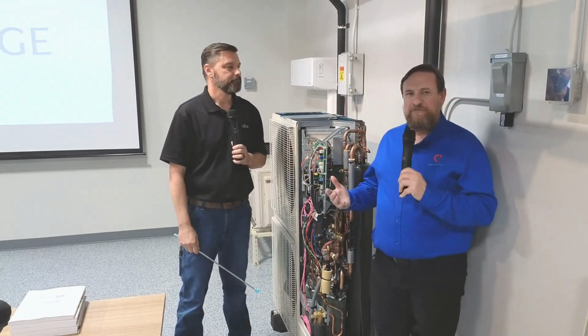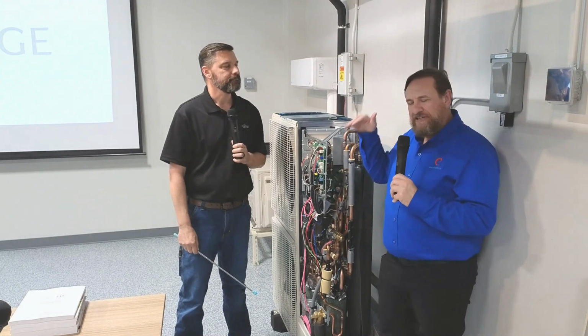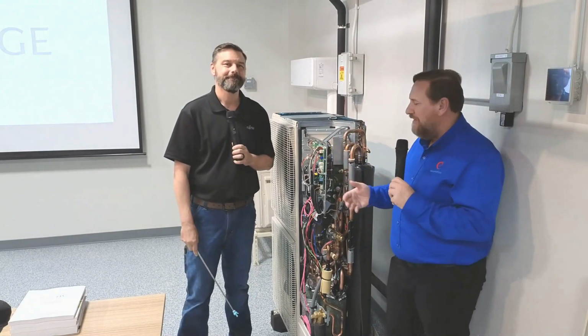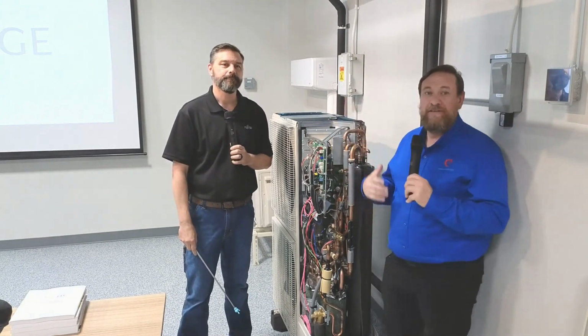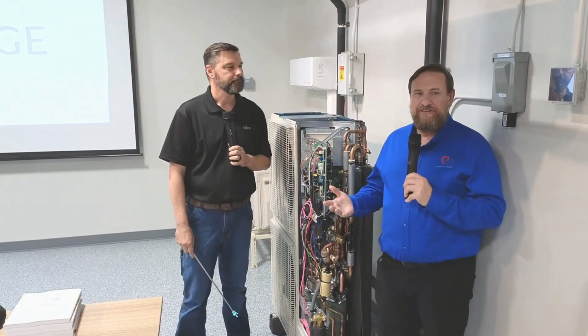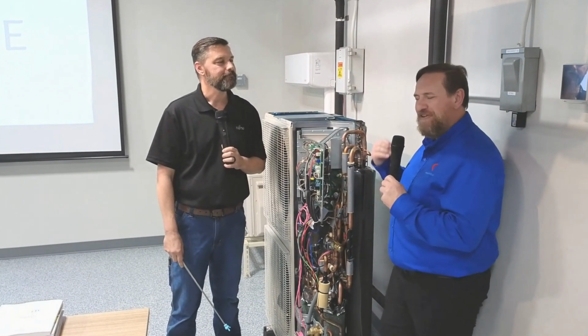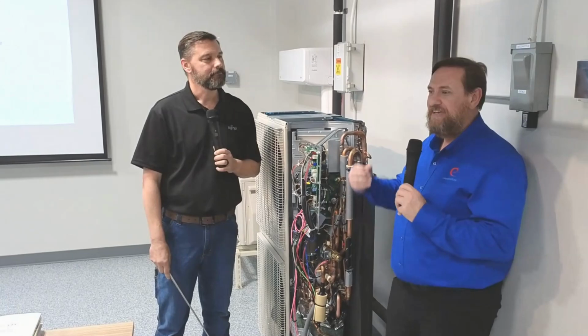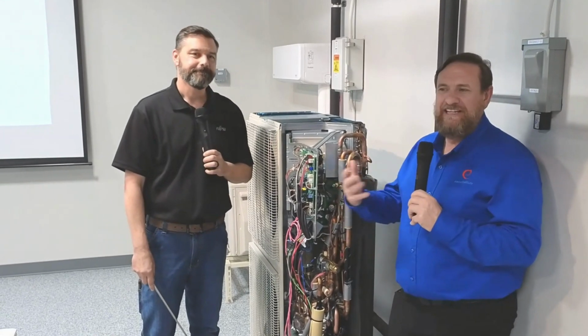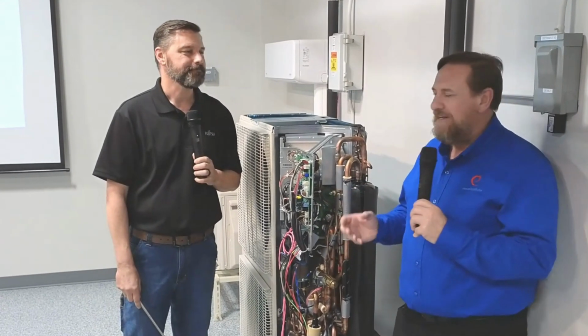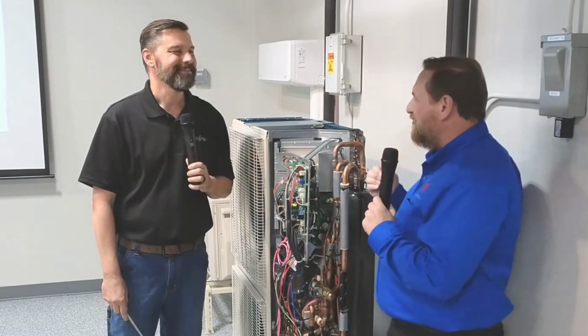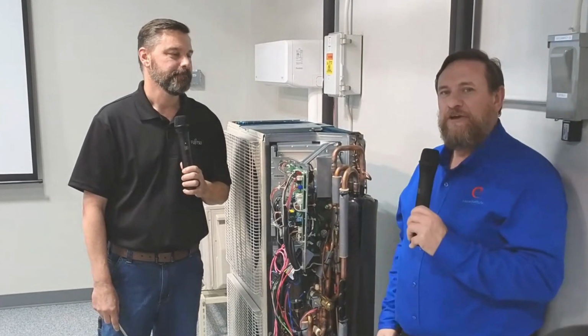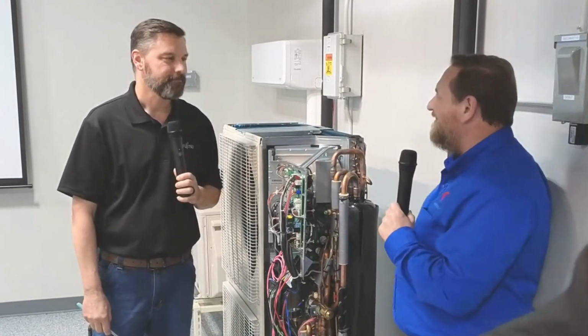We looked at a system that was low on refrigerant, and we could see the tracking from the graphs through the tool. We also had error codes pop up to let us know we had a low refrigerant system. Now, if we're low on refrigerant, one thing that was stressed in the class was leak checking. Before, we'd leak check for a little while, but here, because we want to make sure there are no leaks and we have more connections, they're pressure testing up to 600 PSI for how long?